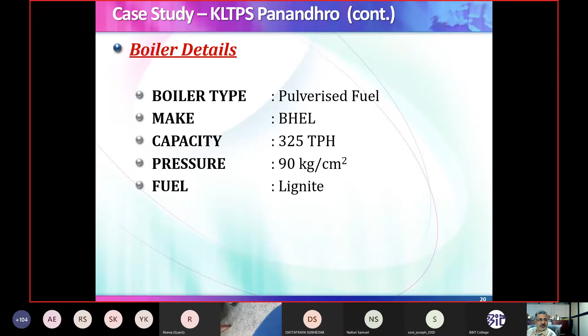Lignite is a very dangerous fuel. It creates a tremendous problem when you fire it into a boiler. So I suggest these were the problems: heavy clinkering in the furnace zone, heavy fouling in the suction duct, and excess SO2 due to high sulfur. Lignite is a high sulfur fuel. So the solution I worked out is the SCA.